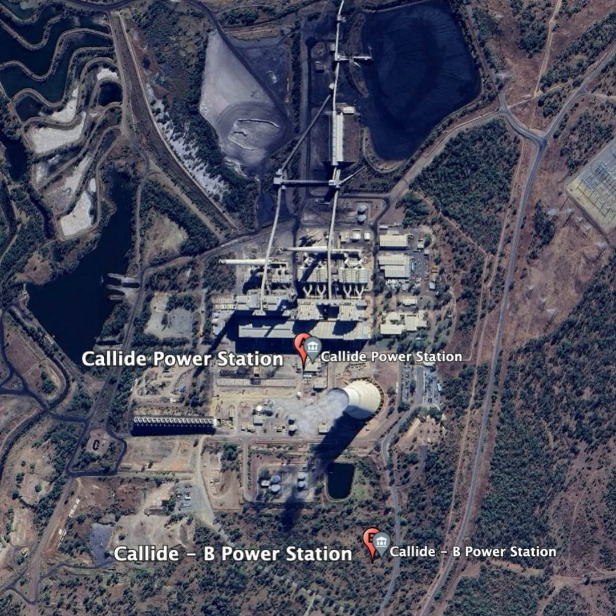The power flow shifted from existing baseload plants to the Queensland-New South Wales Interconnector, or QNI, peaking at just over 1 gigawatt, noting that nominal power flow is 600 megawatts on QNI, before automatically tripping for 16 seconds and then automatically reclosing again by design. This interruption pushed the Gladstone Power Station Units 2, 3, and 4 to trip, and with the Queensland grid now isolated, the base frequency shifted to 48.53 Hz, which then started under-frequency load shed relays throughout the state that started triggering at frequencies less than 49 Hz.